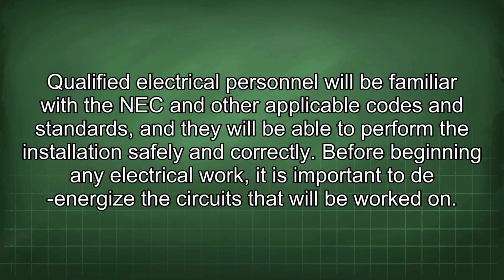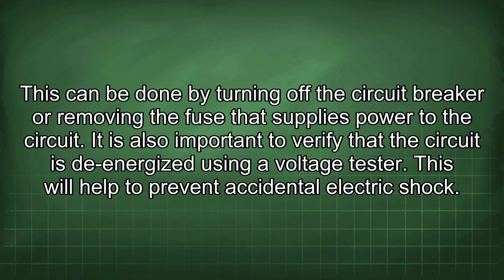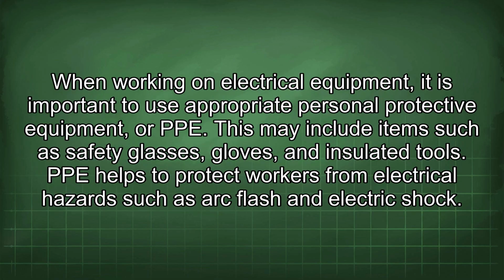Before beginning any electrical work, it is important to de-energize the circuits that will be worked on. This can be done by turning off the circuit breaker or removing the fuse that supplies power to the circuit. It is also important to verify that the circuit is de-energized using a voltage tester. This will help to prevent accidental electric shock. When working on electrical equipment, it is important to use appropriate personal protective equipment, or PPE. This may include items such as safety glasses, gloves, and insulated tools. PPE helps to protect workers from electrical hazards such as arc flash and electric shock.